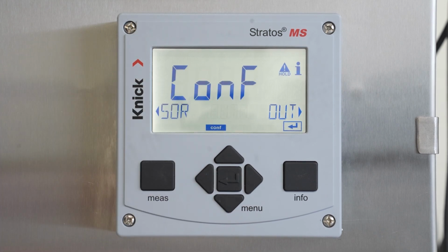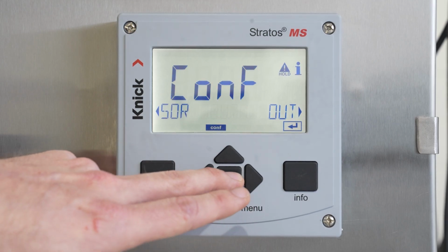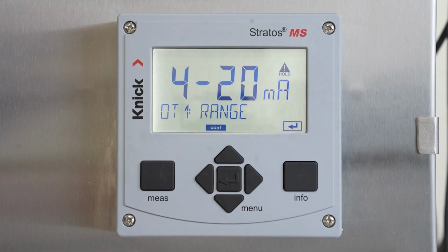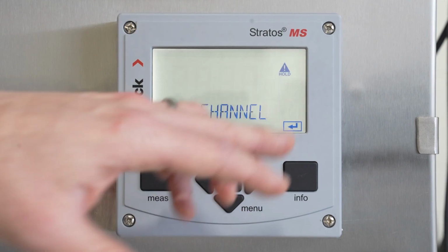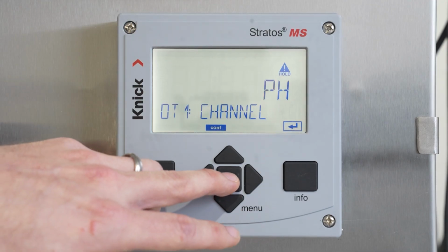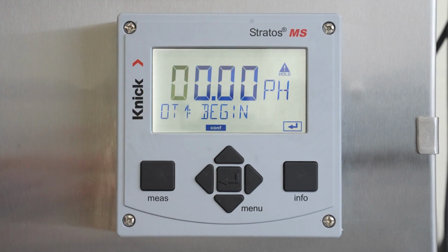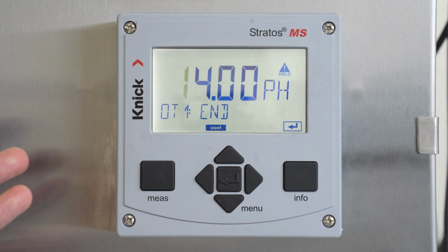Next, we will move to configuration of our 4 to 20 milliamp output. We will select output 1 and range it from 4 to 20 milliamps for pH measurement. Pressing enter here, you will see our begin value, which is equated to our 4 milliamp value. For this video, we will set it from 0 pH to 14 pH, which is the default. The Stratos MS does, however, allow a span from -2 pH to +16 pH.